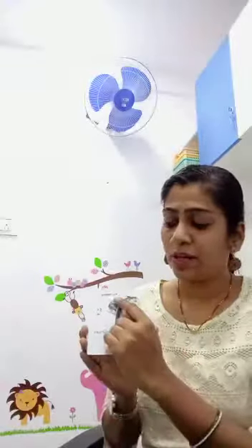For example, the machines which have been in the market, say from the 1990s to the early 2000s, usually used to be very basic analog or very basic digital machines. These machines would have only one microphone. Microphone is the point on the hearing aid which is the pickup point of your machine. These microphones used to pick up all the noise, the speech and the noise, making it a little difficult and straining for the patients.